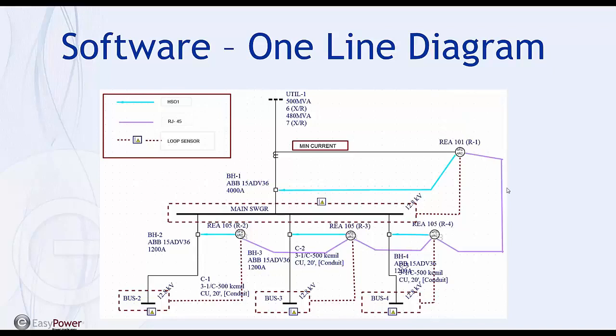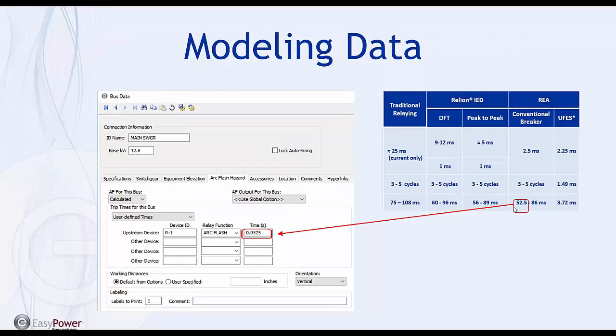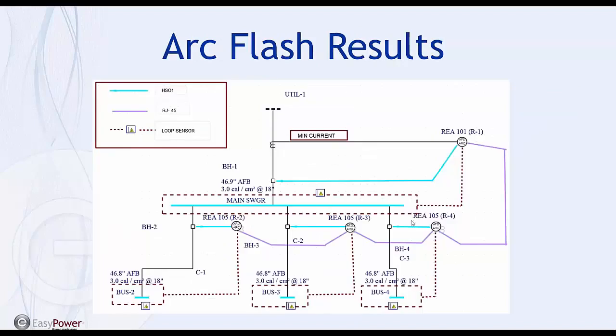You've got to have your current, you've got to daisy chain them, and you've got your sensors. This is the way we modeled it. You've seen this in a previous slide showing the range of all the times for a standard 3 to 5 cycle breaker. And for the REA, it's very fast, 2.5 milliseconds. That gets tacked onto the breaker time. And we looked at a 3 cycle breaker, so that information is provided in the arc flash hazard predefined time for the arc flash unit. And then we can run an arc flash study and take a look at the results and see what the incident energy looks like.